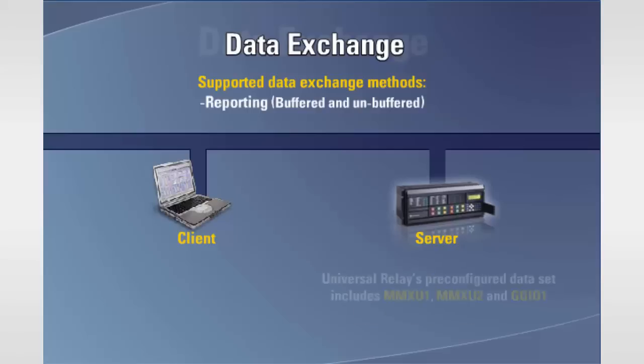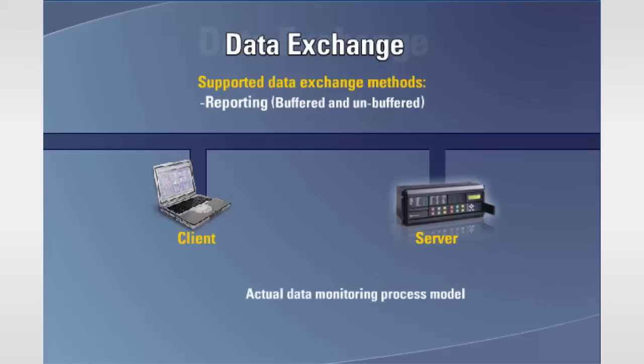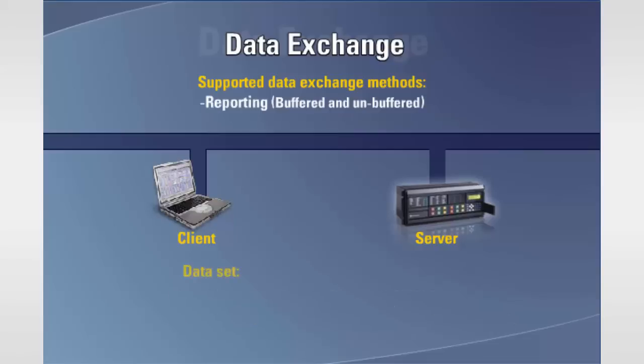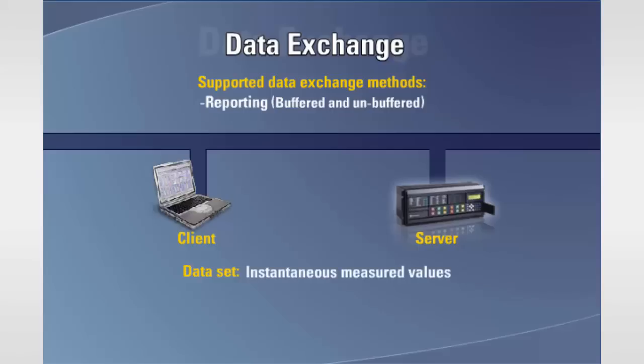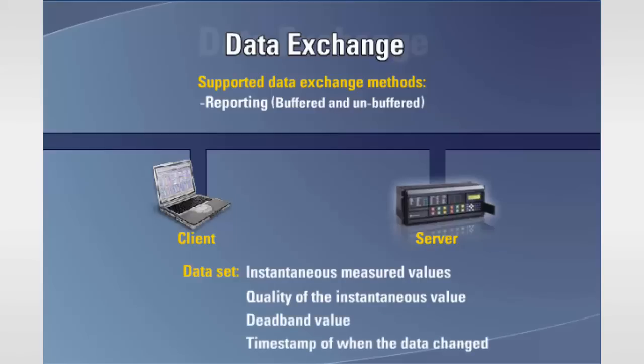The Universal Relay's pre-configured dataset includes MMXU1, MMXU2, and GGIO1. The dataset is grouped and formatted as either logged or report data. Some examples of the information that can be included within the dataset are instantaneous measured values, the quality of the instantaneous value reported, the deadband value, and a timestamp of when the data changed. The report process starts when the client writes the enable. Once enabled, the actual values are evaluated to determine if an event such as a change in state has occurred. Any values within a dataset that have passed the event criteria form a report, which is sent to the client including the trigger or event which caused each data value to be included.